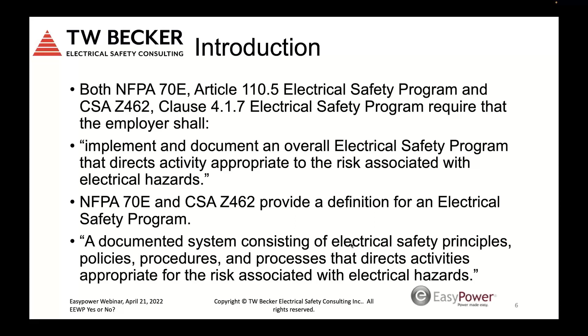A company could strictly say, hey, we're going to need a permit for everything, which I wouldn't sponsor. You do not need an energized electrical work permit for every work task, because you're going to have people doing signatures quite a bit, and it becomes bureaucratic - the permit's not adding any value. So if you misinterpret the permit conservatively, you're getting these permits signed like every day and multiple times when energized work tasks are performed, and that really isn't what you should be doing with the permit.